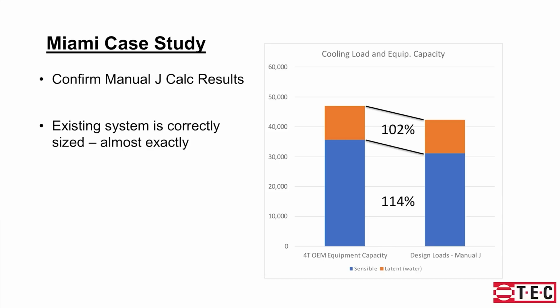And what I've got here on this bar chart is the equipment capacity. The blue is the sensible capacity, and the orange here is the latent capacity. So as you do your sizing, if you're following the Manual S process, you've got to have enough capacity to cover the sensible load and the latent load, or the cooling and the dehumidification.